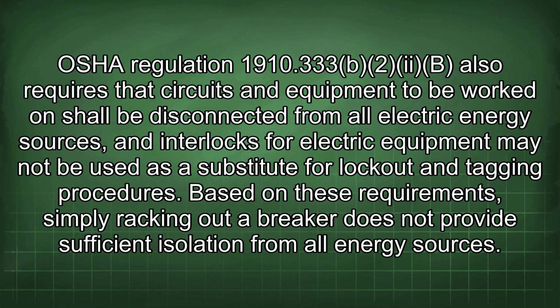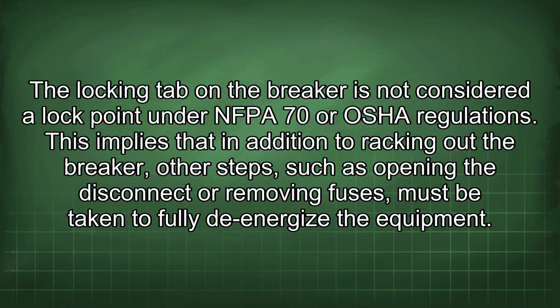Based on these requirements, simply racking out a breaker does not provide sufficient isolation from all energy sources. The locking tab on the breaker is not considered a lock point under NFPA 70 or OSHA regulations. This implies that, in addition to racking out the breaker, other steps such as opening the disconnect or removing fuses must be taken to fully de-energize the equipment.